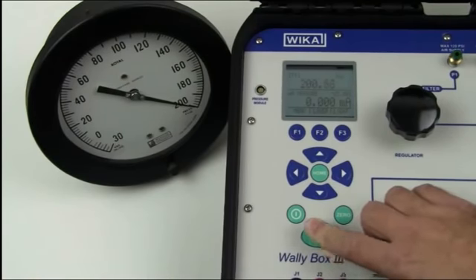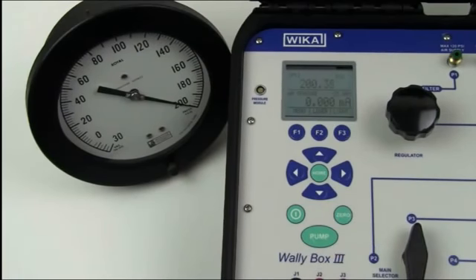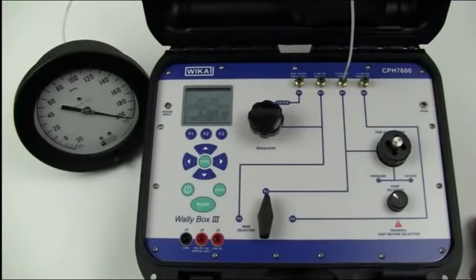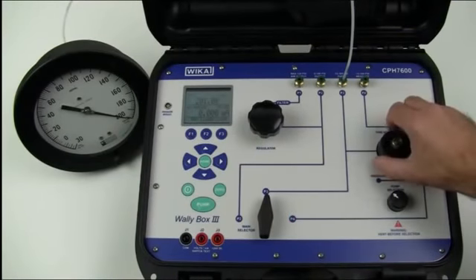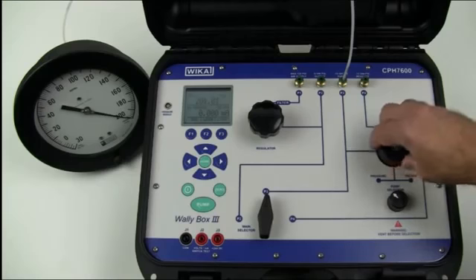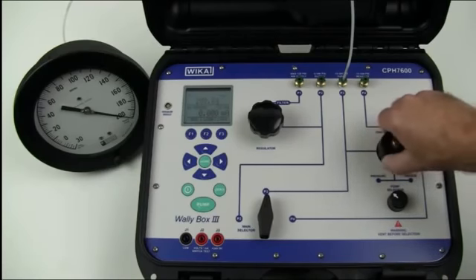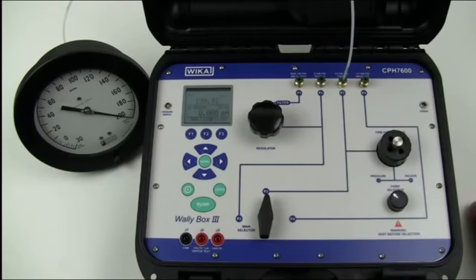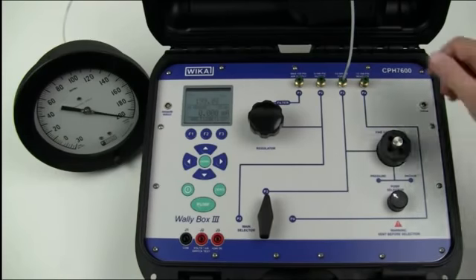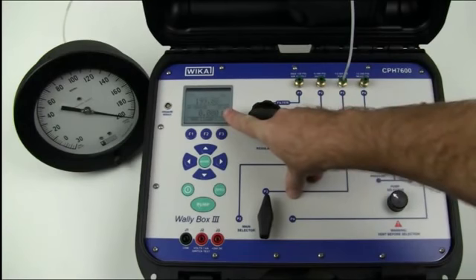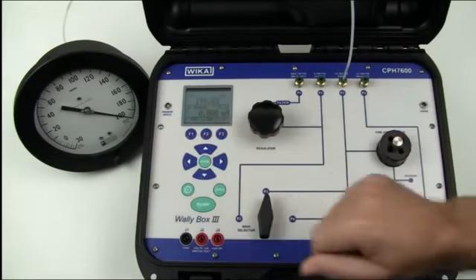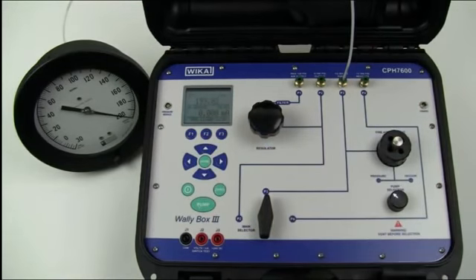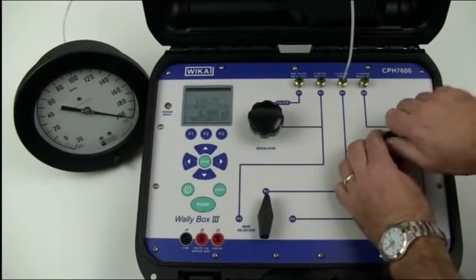You will notice at this point the pump no longer operates and the gauge is at 200 psi. To get the gauge on its cardinal point, you may have to do fine adjustment. You can use the volume adjuster on the Wally Box and adjust the pointer so that it's on 200 psi. You can then read off the Wally Box what is the pressure compared to that of the device under test, and when you are complete, you can vent the system.